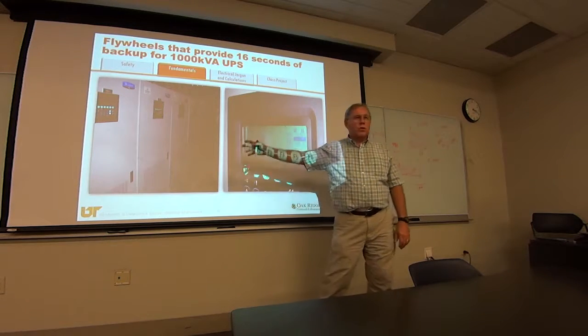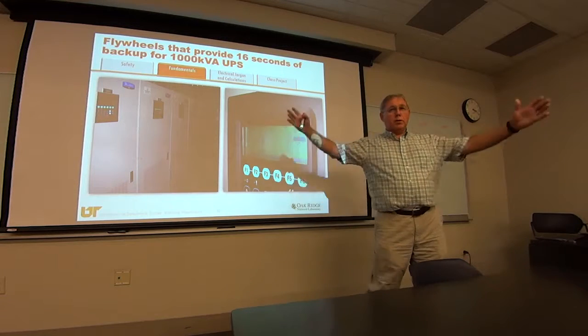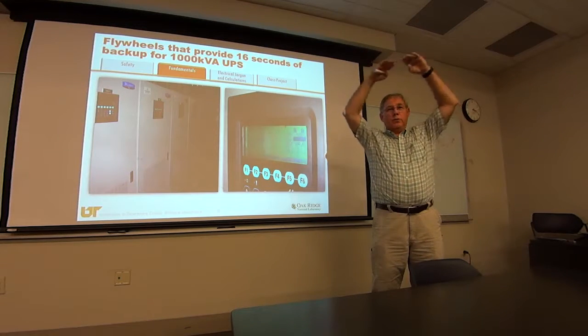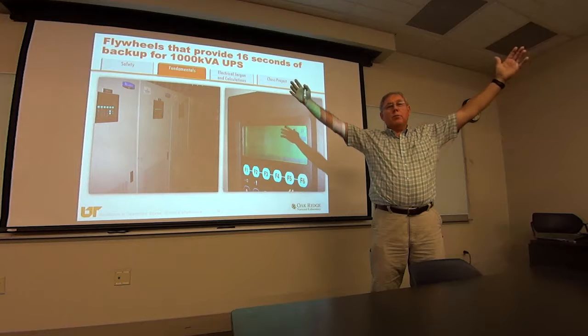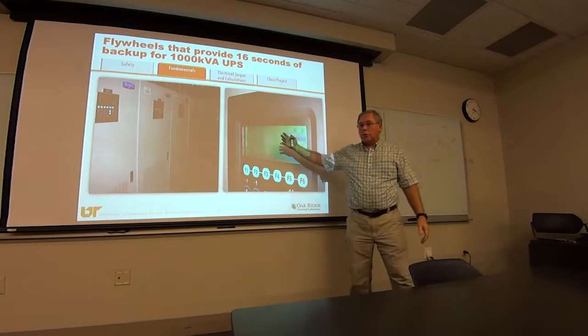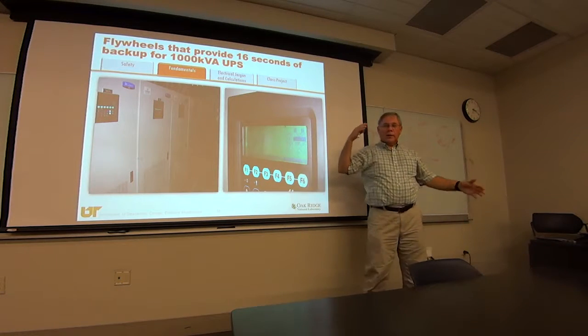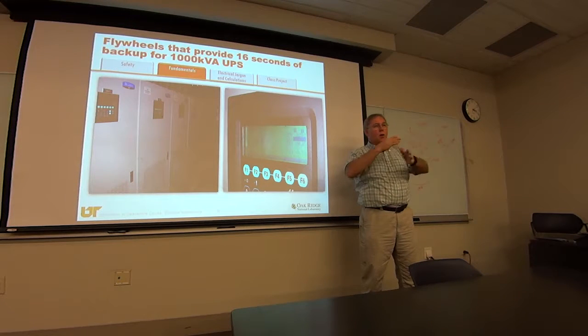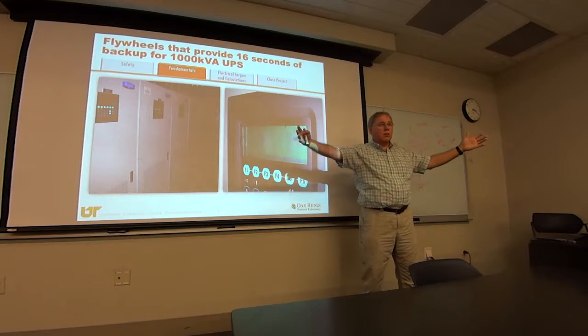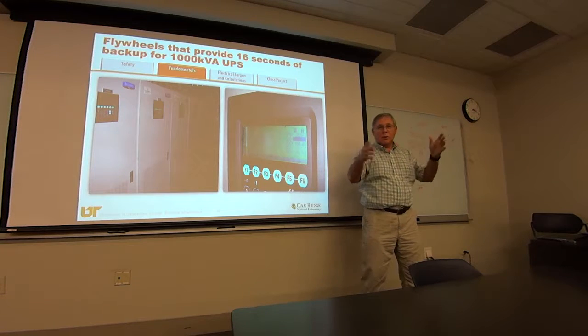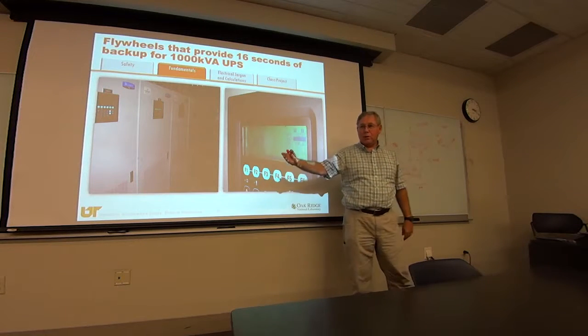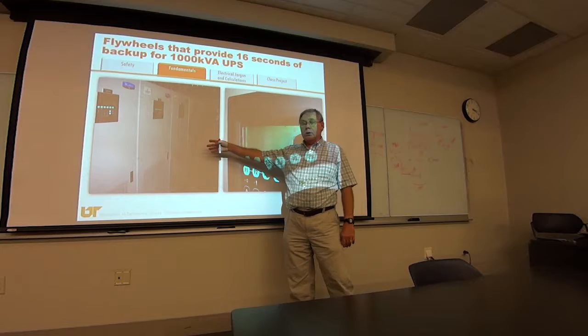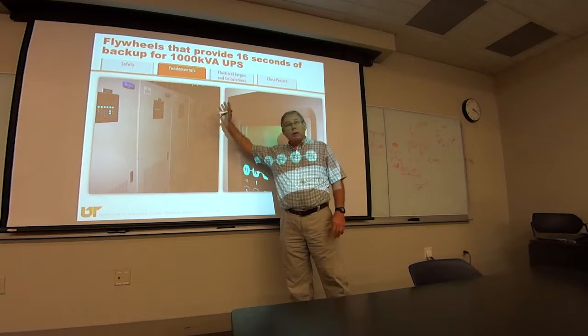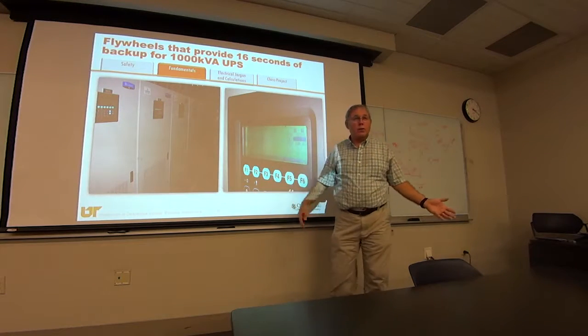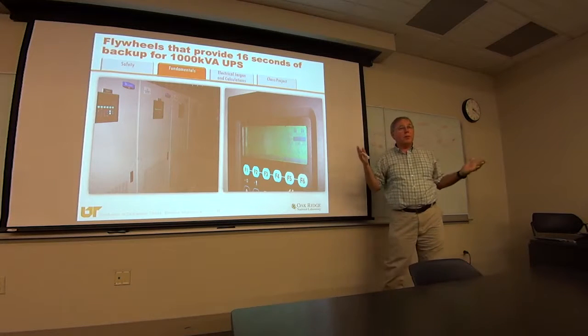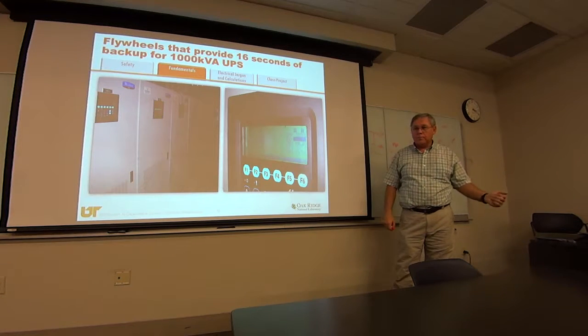Now, I've actually been in places where they had buildings that were full of batteries for their UPSs, and they had to run like 30 minutes because they had a bunch of generators that got off battleships, and synchronizing those things was a dog. They had about 10 generators in parallel, and they'd have to wait 30 minutes before they got them all synchronized, so they had to have UPS that ran long enough. This one right here has got 1 generator on it, 7 seconds. I just need 16 seconds of UPS because if I don't get the generator started in 16 seconds, it's probably not going to start, and it doesn't matter anyway.